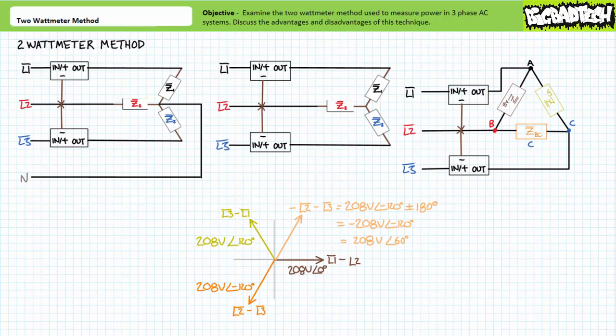How can this be true? I'd explain, but it'd be a waste of time since it's a mathematical goat show of epic proportions and absolutely not essential to the implementation and practical use of the two-watt meter method. Long story short, I like to think of the two-watt meter method as a means of indirectly monitoring any imbalance in the system by keeping a hand on two lines — i.e., the two line current ammeters — and a foot on the other, making use of the other line as our reference. With three points of contact, the truth can be squeezed from this system. Note the two-watt meter method is entirely external to the system. It works for either Y or delta configurations, and it's a lot easier to implement than the three-watt meter method.